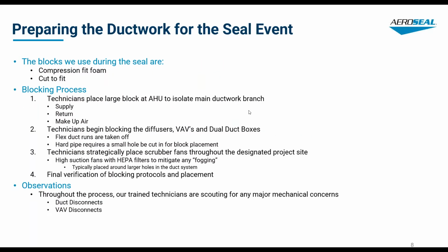So, preparing the ductwork for the seal event. We talked about earlier that the technicians are going to set up the ladders where they need them. The blocks that we use are compression fit foam, cut to fit. We cut them about a half inch bigger, and then we squeeze them into the opening so that they'll be an airtight seal. Technicians will place a large block at the air handling unit to isolate the main ductwork, supply, makeup air, or return, whichever branch we're working on that night.